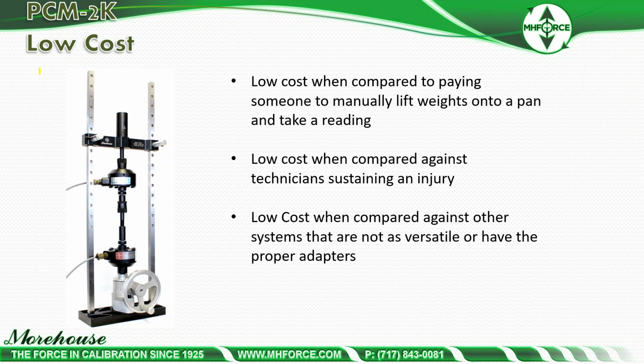No one really ever evaluates what it does to the end user when you have high uncertainties, and they never evaluate what the wrong adapters do to the measurement chain. And I can tell you that if your measurement's off, that bias will carry through to every subsequent measurement down the chain, and it will get worse and worse and worse.